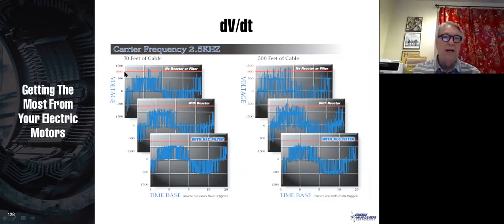Notice that the red line is at 1000 volts, and the top of the graph is 1600 volts. That's really nice because the 1000 volts is your standard motor, NEMA MG1 Part 30. The top of the graph is your VFD rated motor, NEMA MG1 Part 31. Now you get all these little spikes coming out of the VFD, and you will notice over here that some of those spikes are barely going above 1000 volts. So if you had a standard motor, in theory, this could cause premature motor insulation failure.